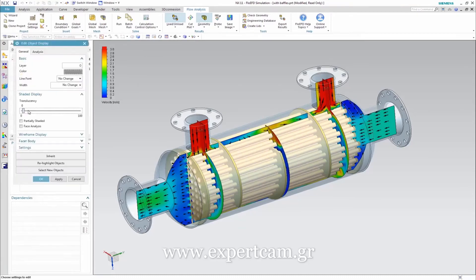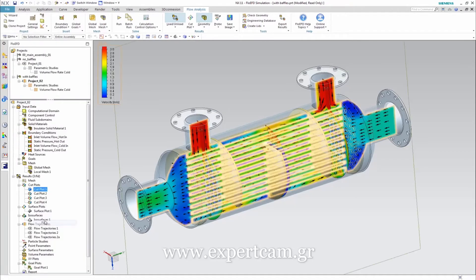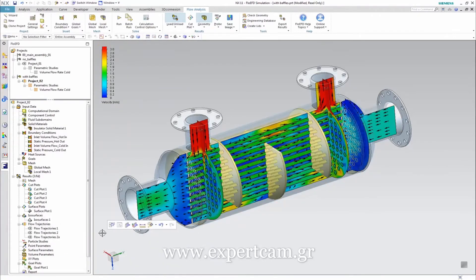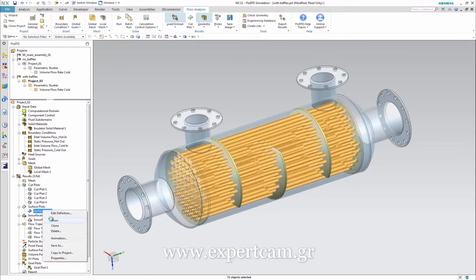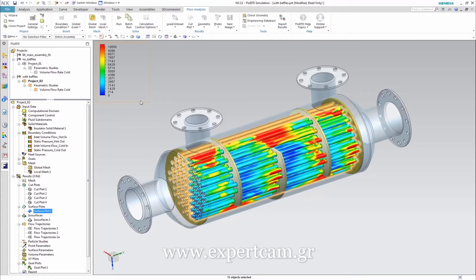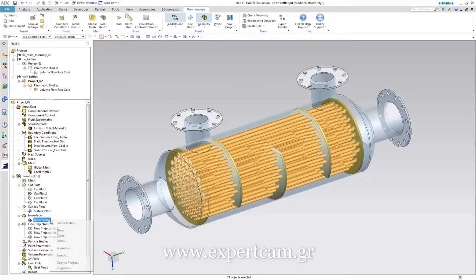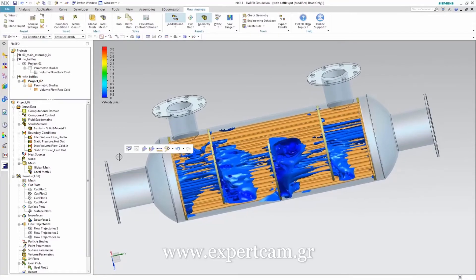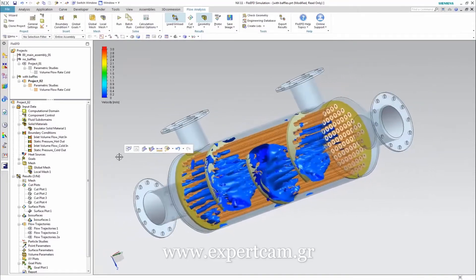Let's change to a transparent view. Here we can see again the cut plots and the influence of the additional baffles in the current configuration. The surface plots show a somewhat more even distribution of the velocity. The heat transfer coefficient is the same, and also for the temperature. Looking at the ISO surfaces again, they no longer show such a large expansion. However, there are still zones with a very low velocity.